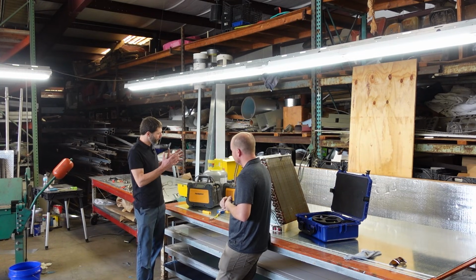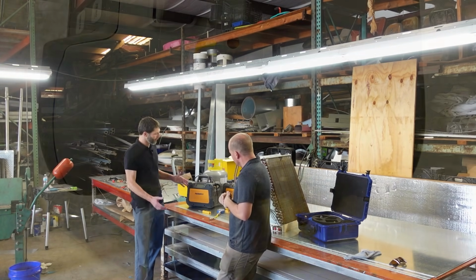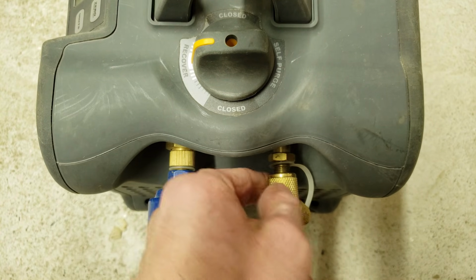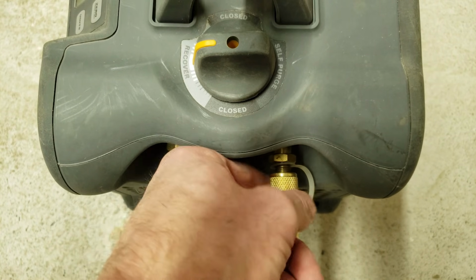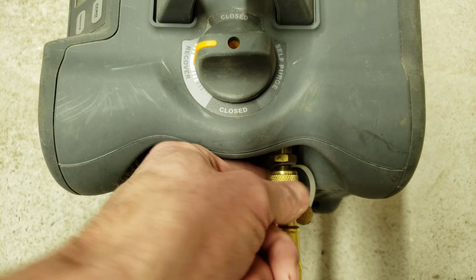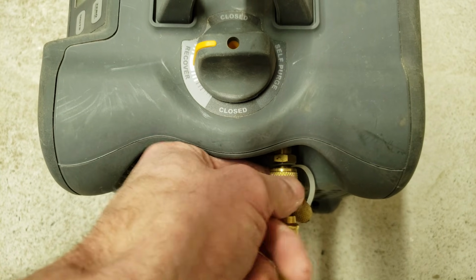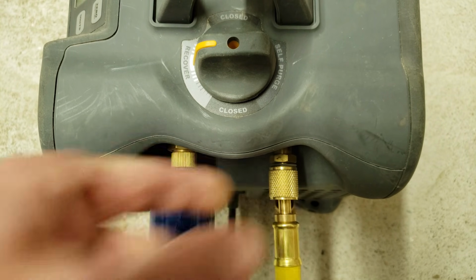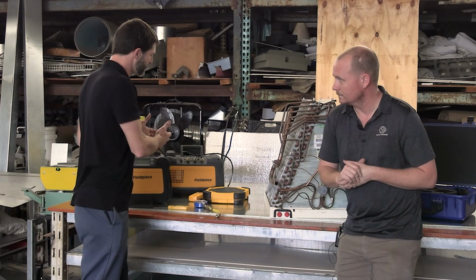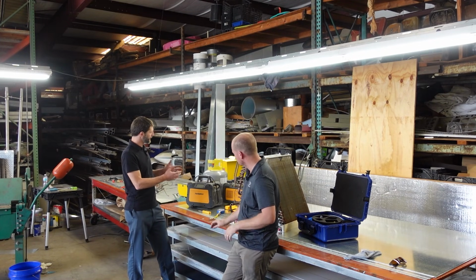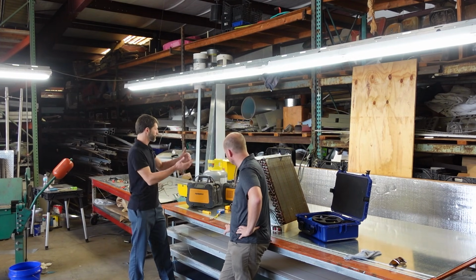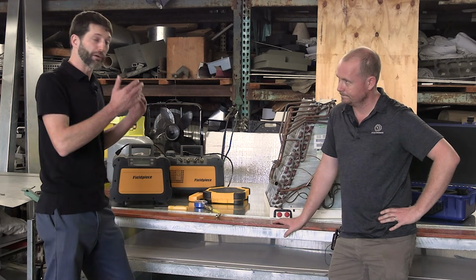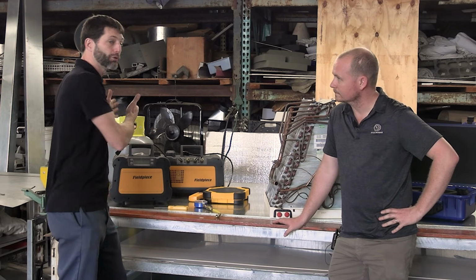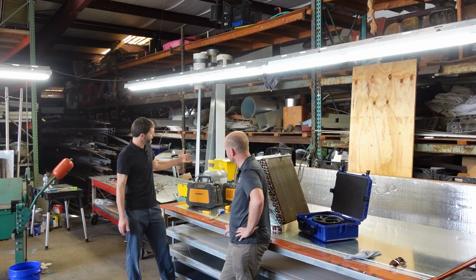Right. Basically, when you hook up a recovery machine, you want to make sure that all of your hoses are snug, but you don't want to crush the rubber on the hoses onto the port connections. So you're really closing down the pathway, but as well, you don't want them too loose to where they're vibrating or something like that during your recovery, and then all of a sudden you're pulling air into your recovery machine and then forcing it into that recovery tank.